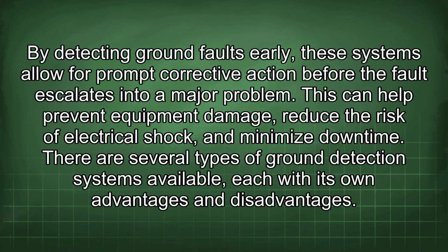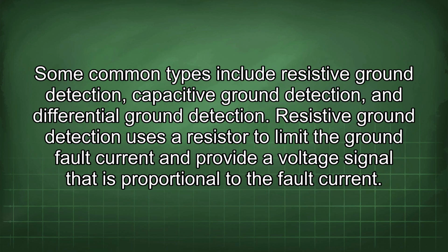By detecting ground faults early, these systems allow for prompt corrective action before the fault escalates into a major problem. This can help prevent equipment damage, reduce the risk of electrical shock, and minimize downtime. There are several types of ground detection systems available, each with its own advantages and disadvantages. Some common types include resistive ground detection, capacitive ground detection, and differential ground detection.